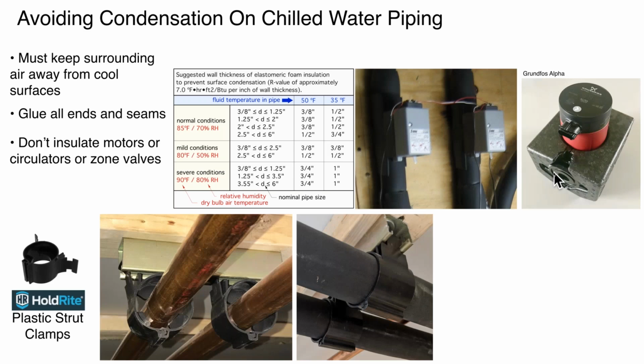It is important when you use these shell products that you seal the seams up. Remember, if air can move and get in contact with that surface, whatever it is, whether it's a valve or a circulator volute or a pipe, you're going to have condensation.